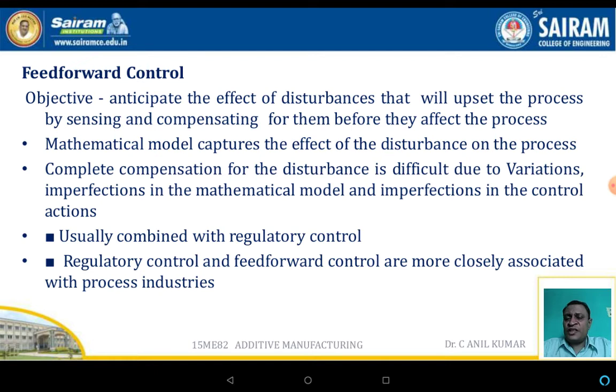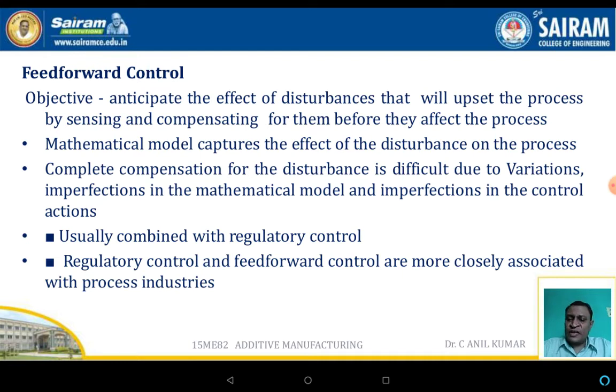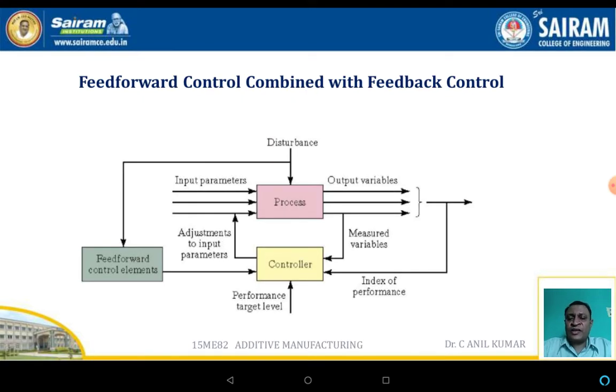The feed forward control system addresses this issue. The main objective of the feed forward control system is to anticipate the effect of a disturbance that will upset the process by sensing and compensating before it affects the process. Mathematical models capture the effect of the disturbance on the process. Complete compensation is difficult due to variations, imperfections in mathematical models, and imperfections in the control actions. Feed forward control is usually combined with regulatory control systems, and both are closely associated with the process industries.